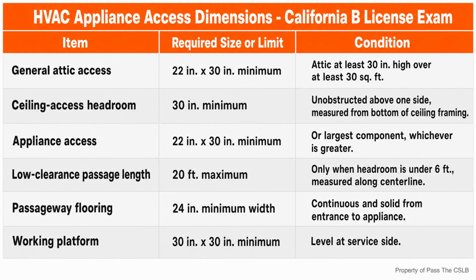Now let's get into it. An appliance is not truly serviceable just because the installer managed to place it in the attic, crawl space, or roof location. The complete route has to work. A person must be able to enter, move to the equipment, see the path, stand or kneel at the correct side, use service power, and eventually remove the largest component. I want that idea to stay at the center of this lesson. Access is a chain, and one bad link can make the entire installation fail inspection or require expensive rework.